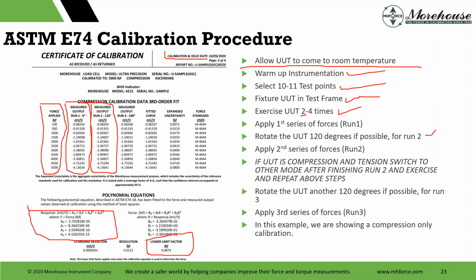This is kind of randomizing the conditions. If it's compression and tension, we switch to the other mode. And then we exercise, like I said, in this case, we're going to exercise probably 4 times to get everything out. And we'll do everything, if we're in the other mode, we do all of it, 1, 2, and 3 in the other mode. Then we switch back to the mode that we started in. Or if this one was compression only, we just ignore this step and just go right to run 3, calibrate it, report it on the certificate.